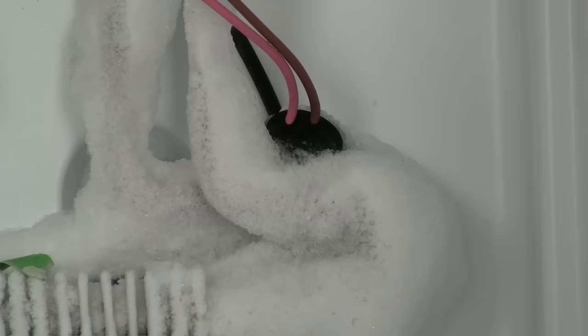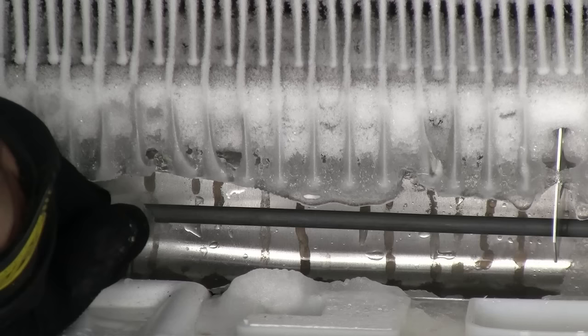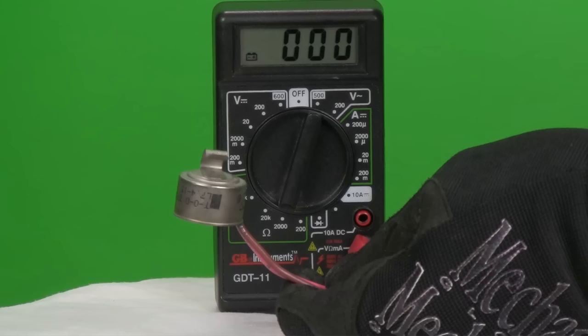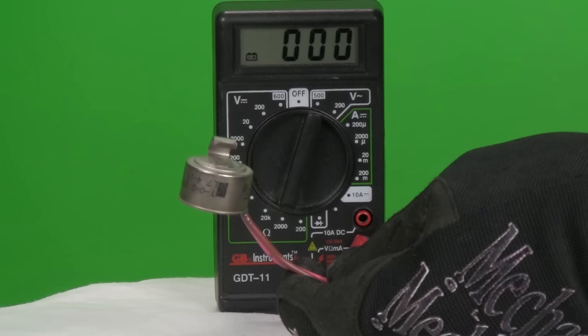If the thermostat is cold enough to be closed, electricity passes through it allowing the heater to be energized. The heater temporarily becomes red hot melting all the accumulated ice until the timer stops supplying power or the bimetal thermostat warms up enough to open breaking electrical flow.